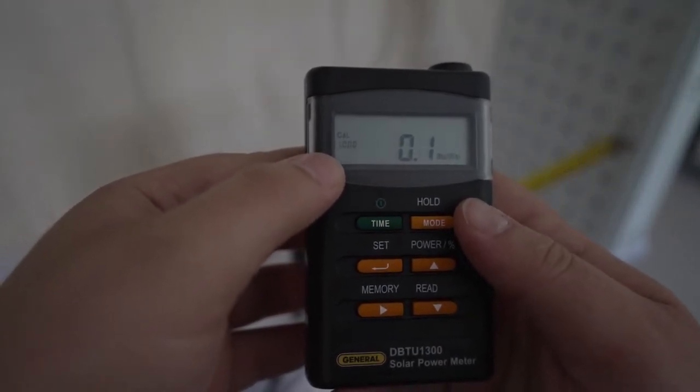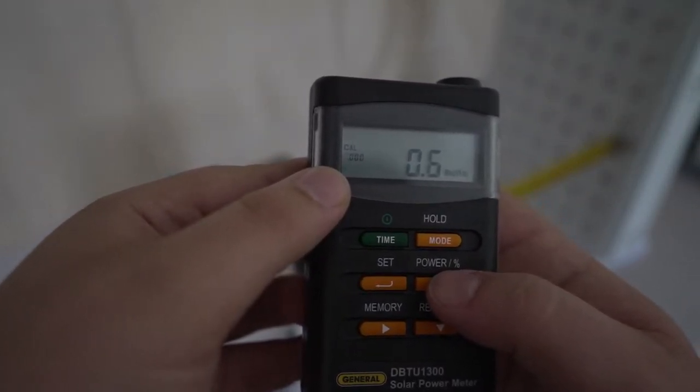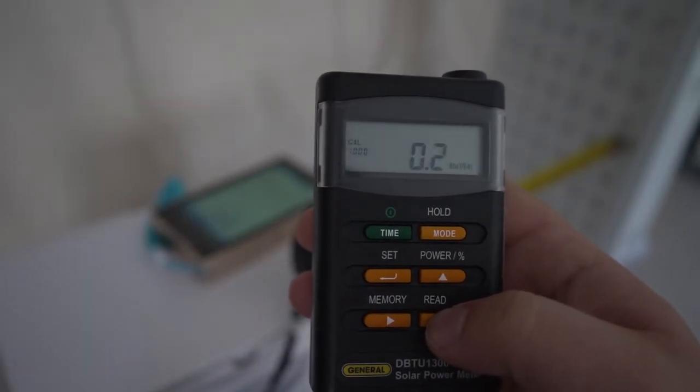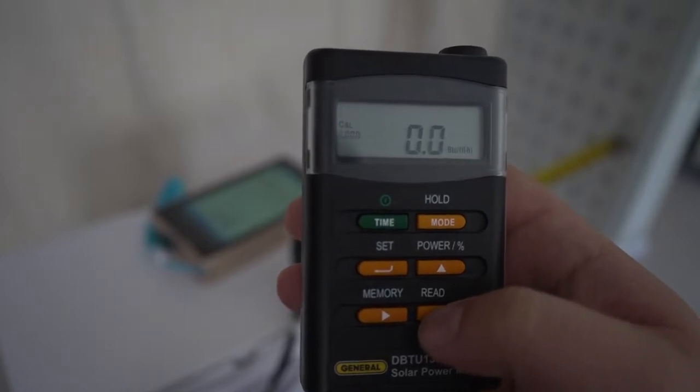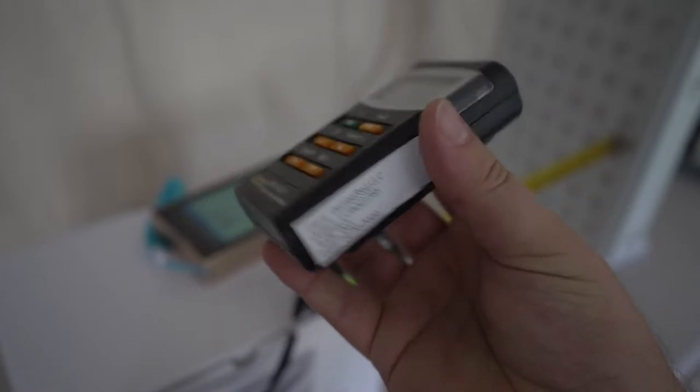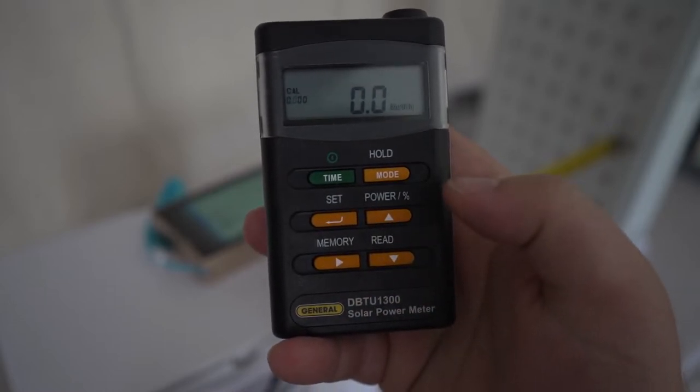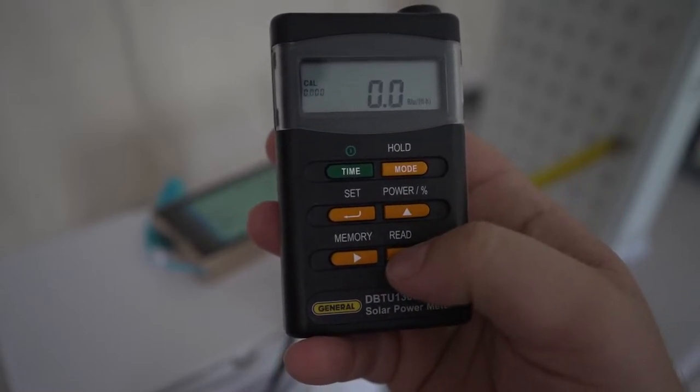And now we see that the number one in the cal is blinking. So that means I can change it now. So we know these read falsely high by almost 2x. And the more precise number that I got from my lab data comparing this specific unit to the lab measurements was that we're going to do about 0.55 as the correction factor.